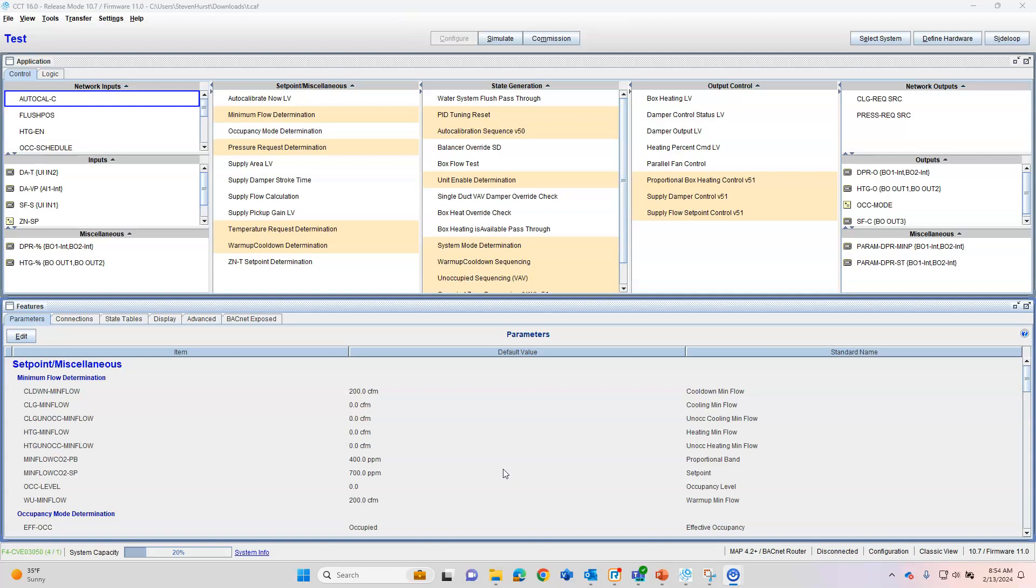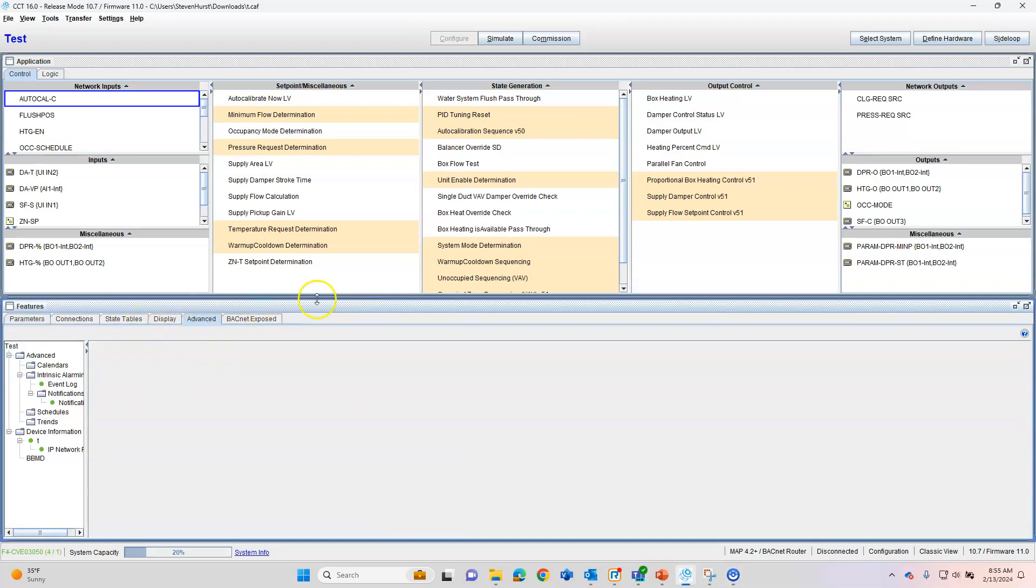The older generation, the PCGs and the FECs, the PCA was the advanced controller that had all the advanced time clock built into it, more memory and all that. On the Johnson side, it would be the FAC instead of the FEC. The A was the advanced controller that had all these features. So schedules, trending, and alarms can all be done under the Advanced tab here on the bottom half of your screen.